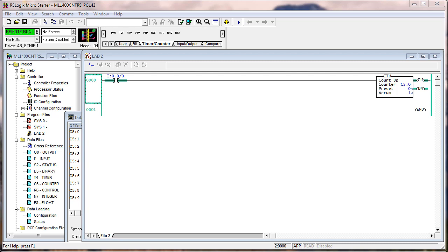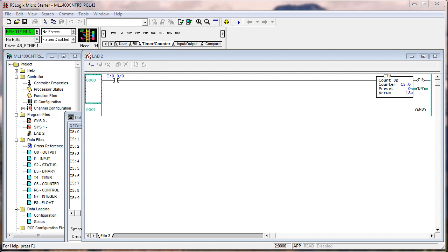When you flipped the switch on, it did its normal behavior and incremented. At this point, every time you toggle input zero on, it's going to increment. The count up instruction is a little different from the timers. Timer instructions count units of time — they don't count false-to-true transitions. Count up and count down instructions react to false-to-true transitions. The preset and accumulate behave the same way as with a timer, but the counter data type will keep counting up or down indefinitely as long as you keep toggling.